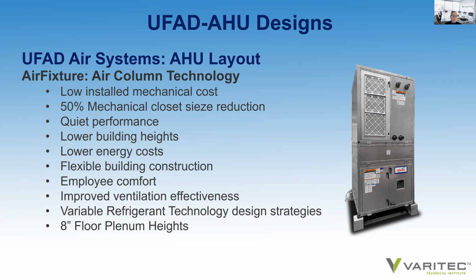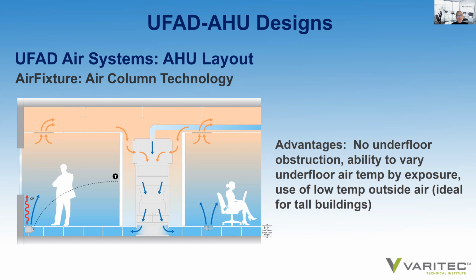They provide tighter control for more energy cost savings, certainly low static pressure requirements for the discharge of air into the underfloor plenums, create greater flexibility of building design, and they are also conducive to 8-inch floor plenum heights. We can also do these units with variable refrigerant coil technologies, which adds a very attractive option to the space, and that's its own topic in itself.